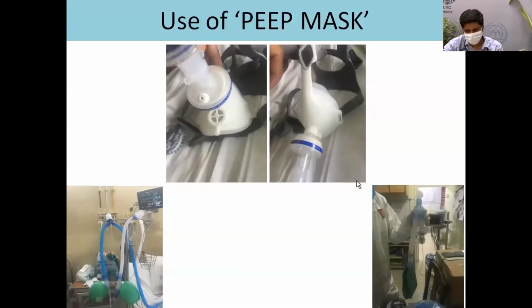And in the modification of this PEEP mask, when you don't have an inspiratory valve, like the NIV mask, this is an additional mask where you have a Y connector, where one limb is attached to the inspiratory port with a reservoir bag, and in the expiratory limb, we have connected a PEEP valve.